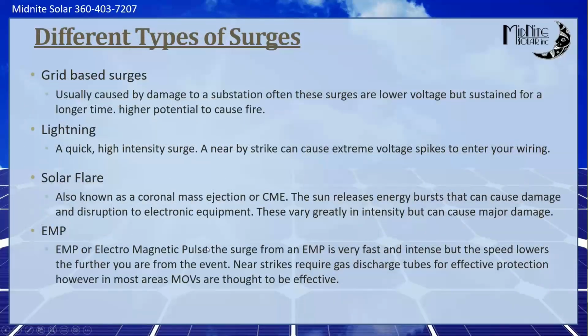So we're going to talk a little bit about surges and what you can do about those, what ones a typical SPD will cover, and what you might need to do for other surges. So you have several types. Probably the most common is surges coming in from the utility grid, be it a lightning strike downstream somewhere on the line, or a substation issue.